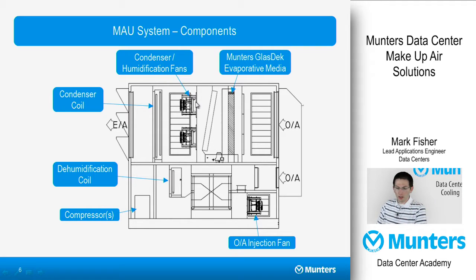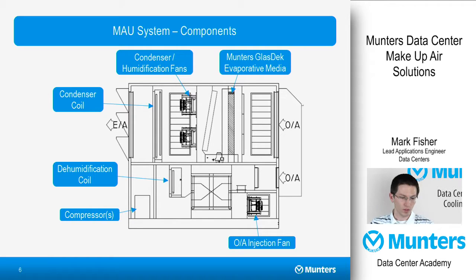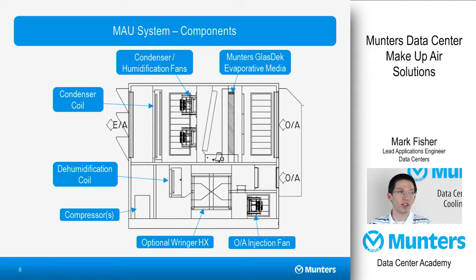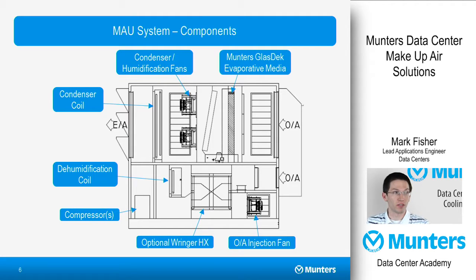The humidification fans become condenser fans during summertime when the DX system is active. To provide additional energy savings, we can incorporate a wringer heat exchanger into the dehumidification side of the system. This will reduce both the operating energy and the peak energy consumption of the system by up to 30 to 40 percent.